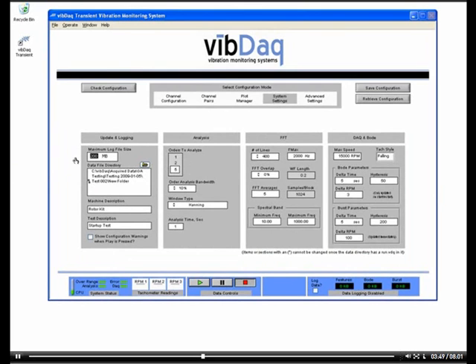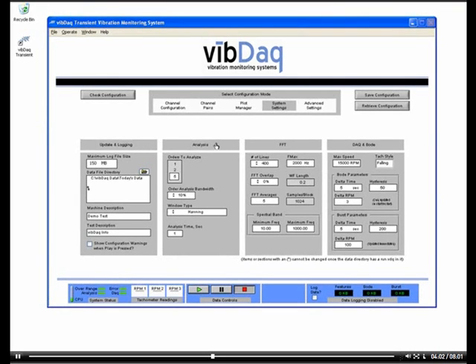One of our initial settings is the data log file directory. We'll also set some parameters related to order tracking so that we can determine the magnitude and phase of input vibrations as a function of tachometer speed, which can be a very useful analysis tool. Another group of settings deals with FFTs and displaying data in the frequency domain. Some of those include number of lines, averages, and max frequency to show on spectrum plots.